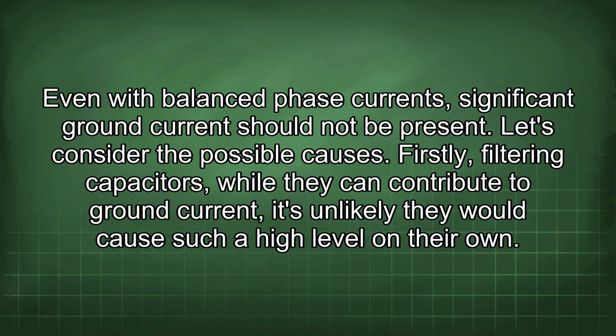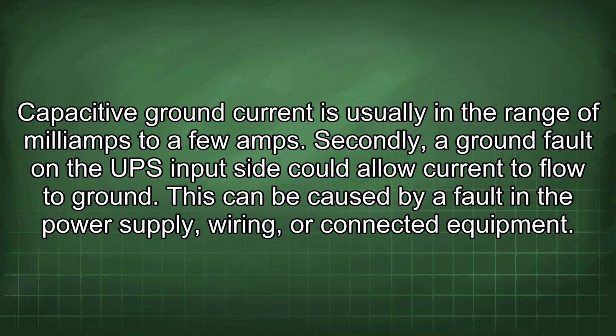Let's consider the possible causes. Firstly, filtering capacitors. While they can contribute to ground current, it's unlikely they would cause such a high level on their own. Capacitive ground current is usually in the range of milliamps to a few amps. Secondly, a ground fault on the UPS input side could allow current to flow to ground. This can be caused by a fault in the power supply wiring or connected equipment.